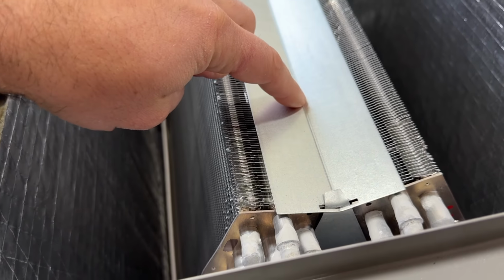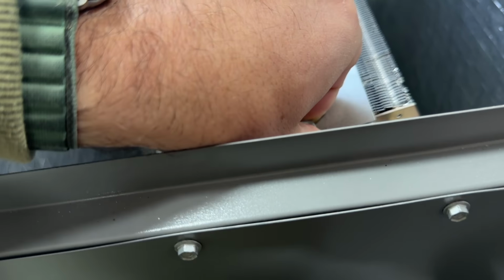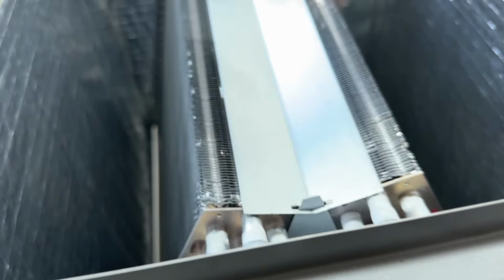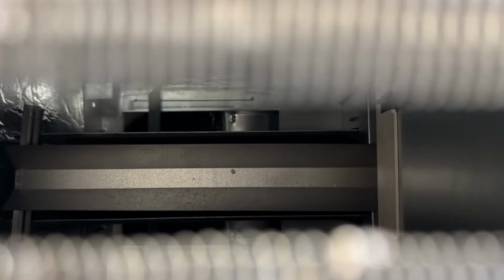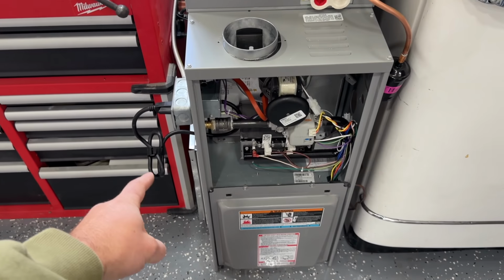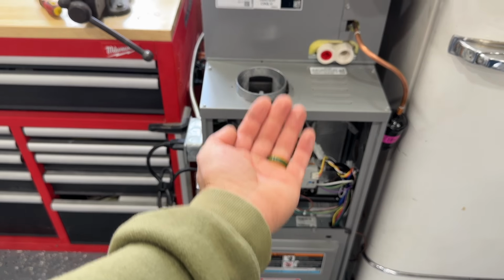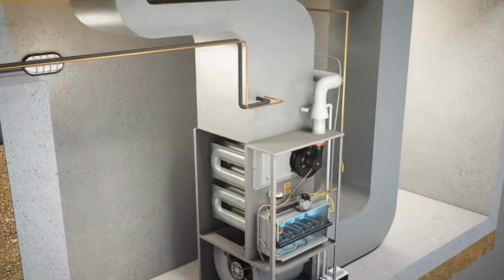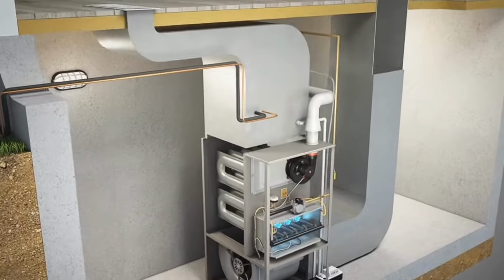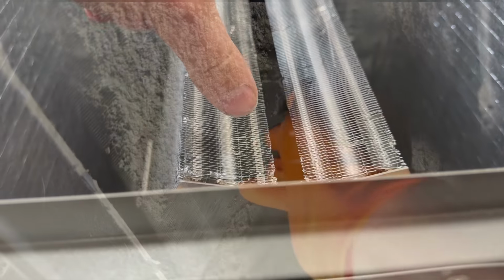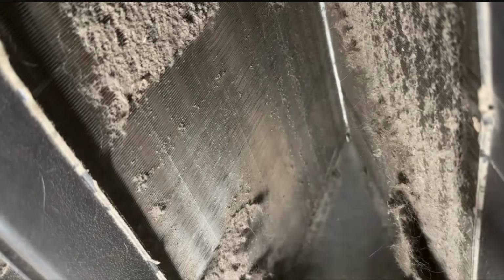But right underneath this top plate, I'll actually take this off so you can physically see what it looks like. So now that I have that off, you can see clear down in here. You can actually probably see that's the heat exchanger right under that metal plate. So what is happening is air is being pulled through the return, it's blowing through the heat exchanger, and it's blowing into the apex of that coil. So right inside of here, this can easily get plugged up with debris and stuff that goes past the filter, and that could be an issue with your heating season.